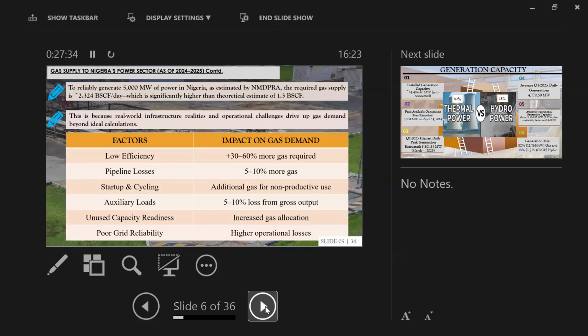And the factors contributing to this in the gas sector: low efficiency, which is about 30 to 60% more than the gas required. Pipeline losses are about 5 to 10%, that is, you need about 5 to 10% more gas. Then startup and cycling, that is ramp up and ramp down of machines, requires additional gas for non-productive uses. Then the gas used for auxiliary load is 5 to 10% of the gross output. For unused capacity readiness, there should be an increase in gas allocation. Then poor grid reliability means higher operational losses.